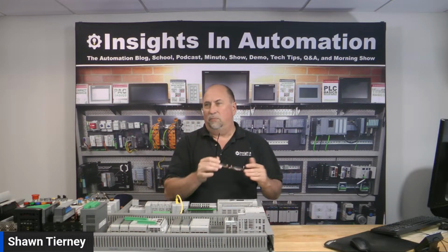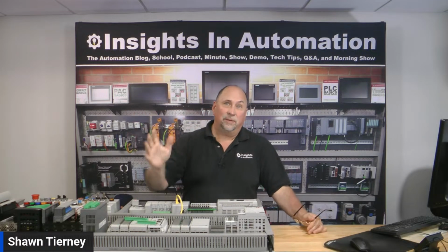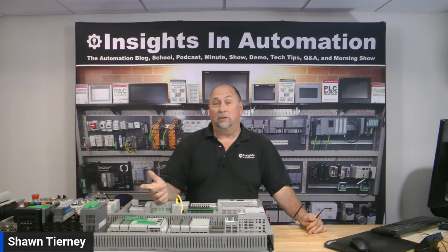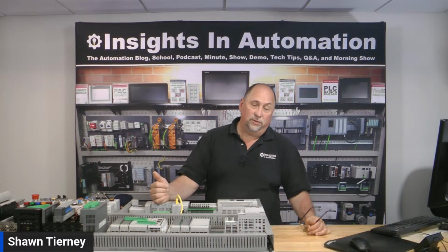You also have to understand what the response time of the I/O is, right? So in 90% of the applications, that may not be a big deal, but in some applications, you may start seeing multiple counts where you only saw one, multiple pulses where you only saw one. You may have current limitations on the new inputs and outputs versus the old ones. So there are a lot of things you've got to consider in one of these conversions.